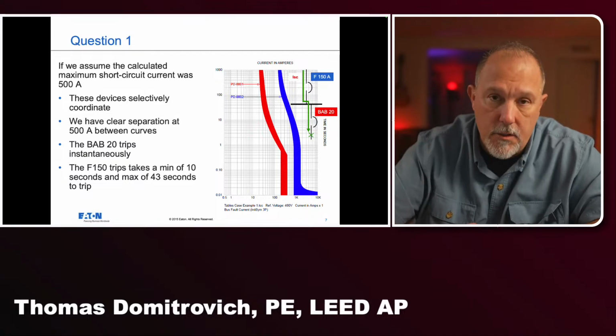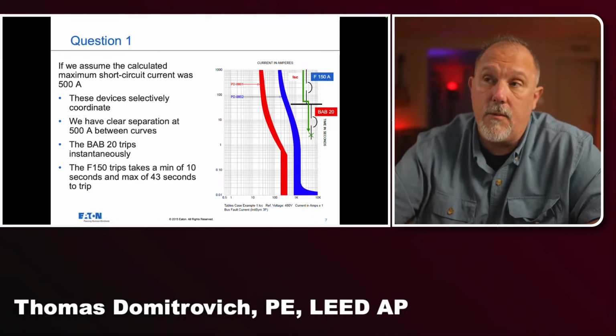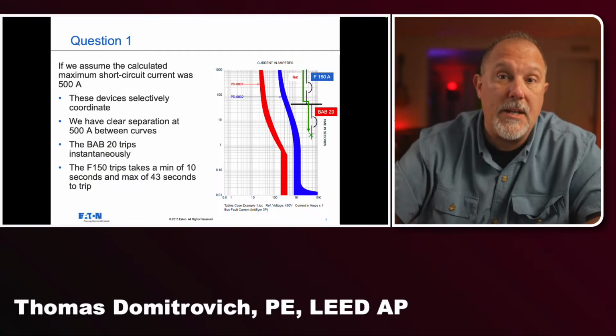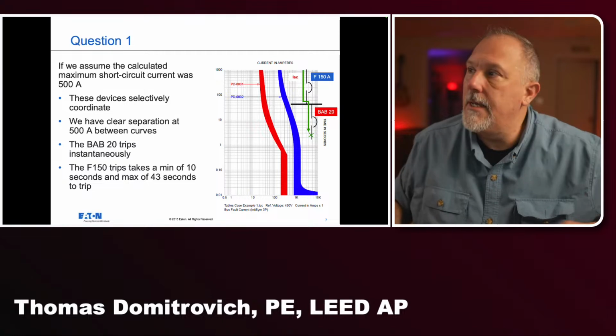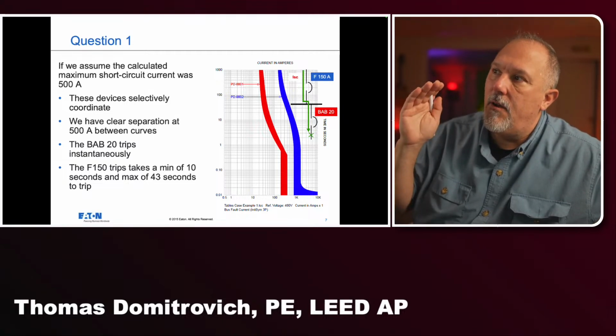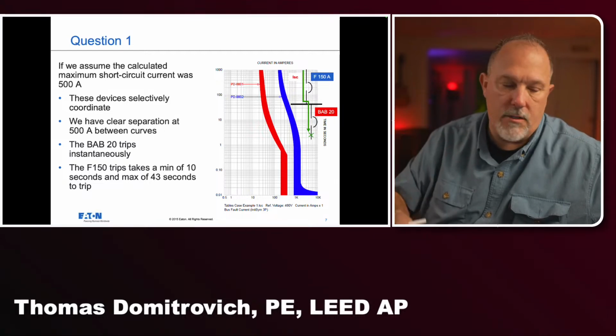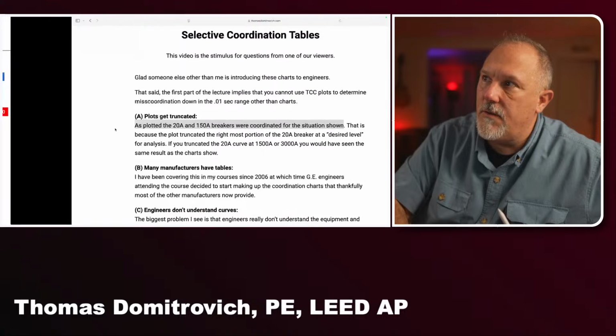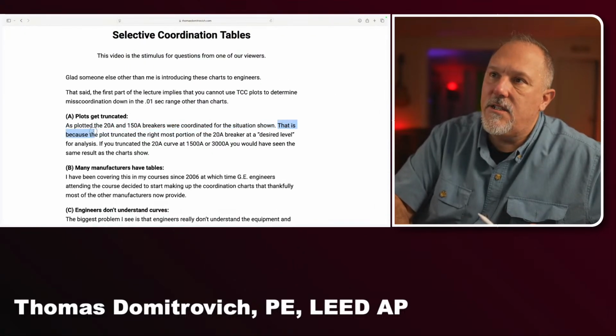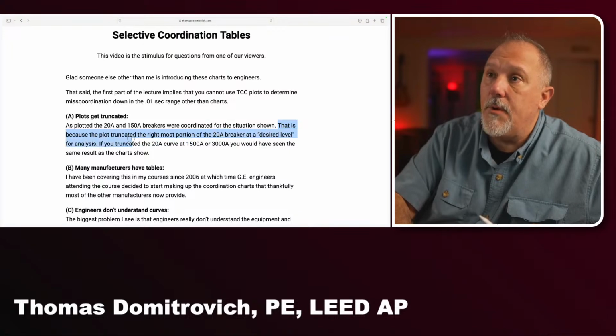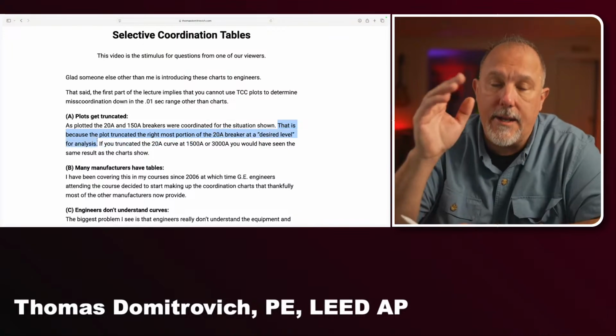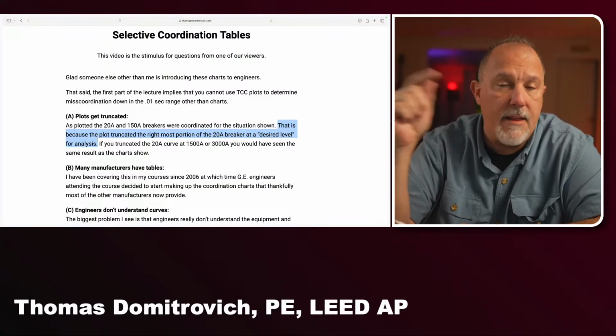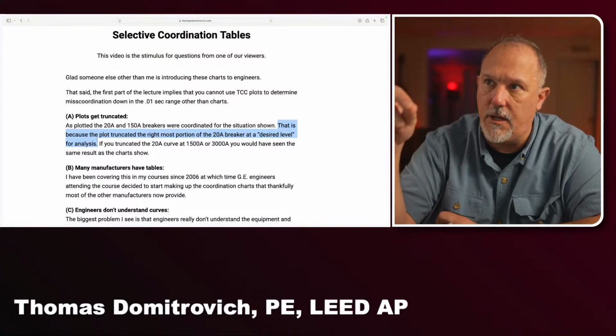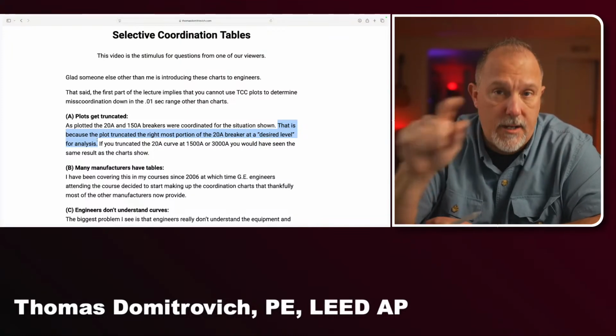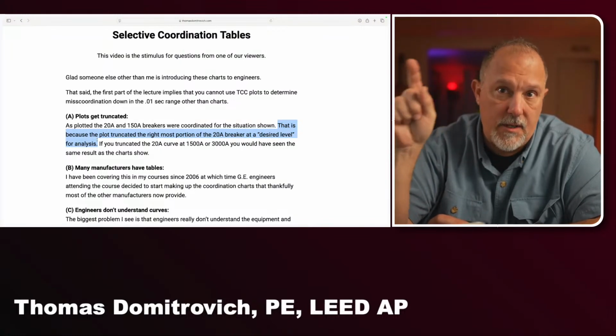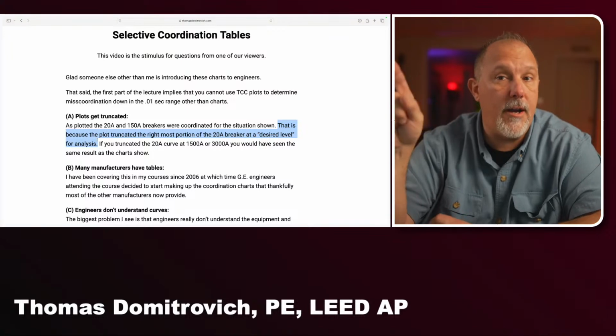Now that could be my overload region, etc. It could very well be a ground fault current, I don't know. Depends on the system. Or an arcing current, depends on the system. But in any case, this curve is not showing the fault currents. So let's go back over to the question. And he says, that is because the plot truncated the rightmost portion of the 20 amp breaker at a desired level for analysis. And I can understand why he may think that. I thought I made myself clear in the video. I have to go back and watch the video. But I'm trying to be clear right now that I'm not showing current on that screen.